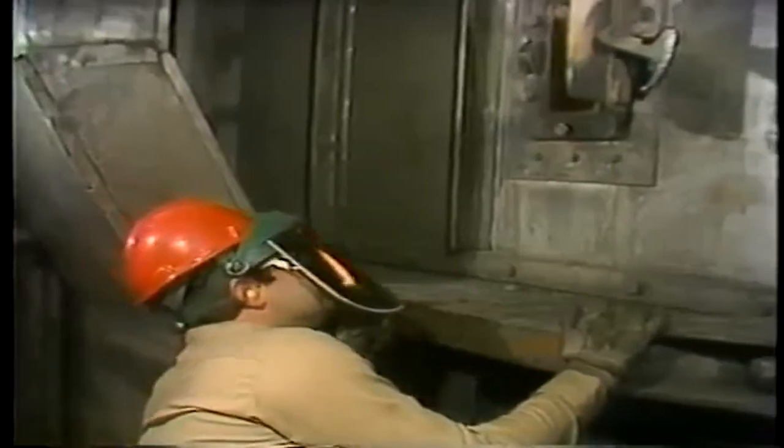The most reliable indication of a boiler flame comes from opening an observation door and actually looking inside the furnace. However, if a loss of flame is suspected, you should not attempt to open an inspection door, as it could cause enough of a draft to ignite the combustibles in the boiler and cause an explosion. If you must make a visual inspection, use the inspection windows near the burners. While television monitors, mirrors, and inspection windows allow an operator to see inside the boiler, none of these indications is totally foolproof. Mechanical or electronic problems with the monitor or camera may give a false indication, mirrors may get knocked out of alignment, and observation windows may be blocked by ash or slag.